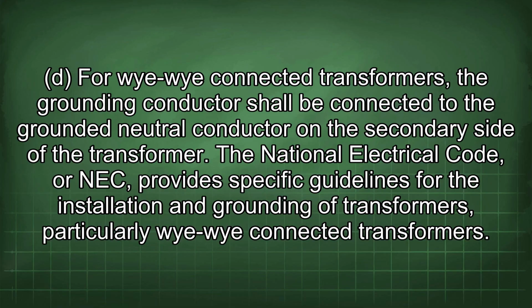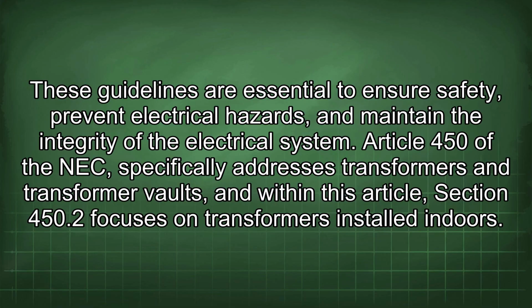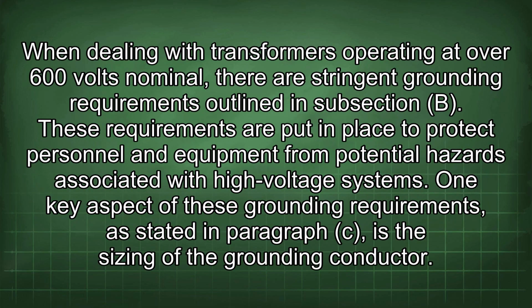of the transformer. The National Electrical Code, or NEC, provides specific guidelines for the installation and grounding of transformers, particularly Wye-Wye connected transformers. These guidelines are essential to ensure safety, prevent electrical hazards, and maintain the integrity of the electrical system. Article 450 of the NEC specifically addresses transformers and transformer vaults, and within this article, Section 450.2 focuses on transformers installed indoors. When dealing with transformers operating at over 600 volts nominal, there are stringent grounding requirements outlined in subsection B.